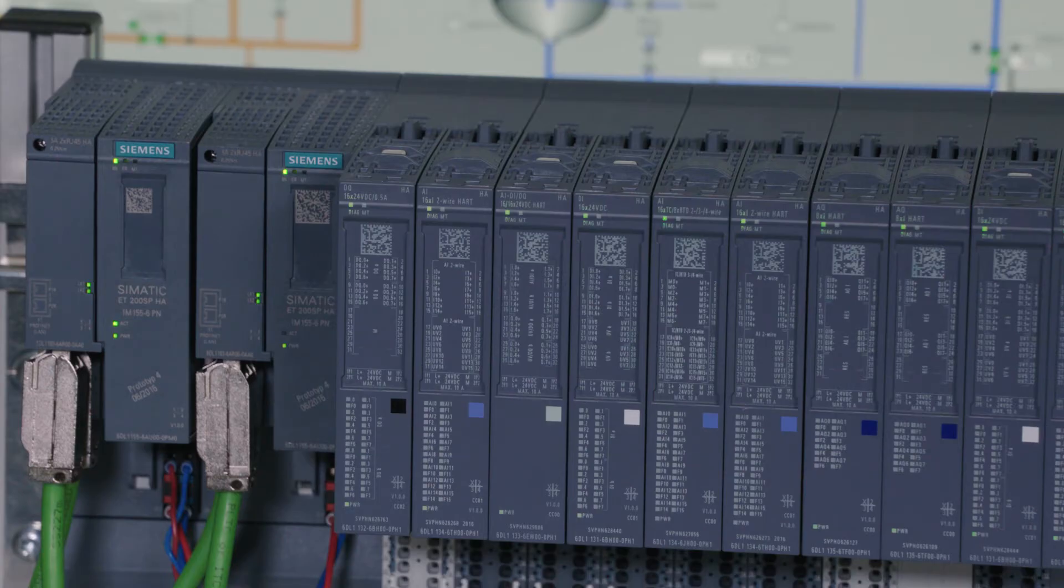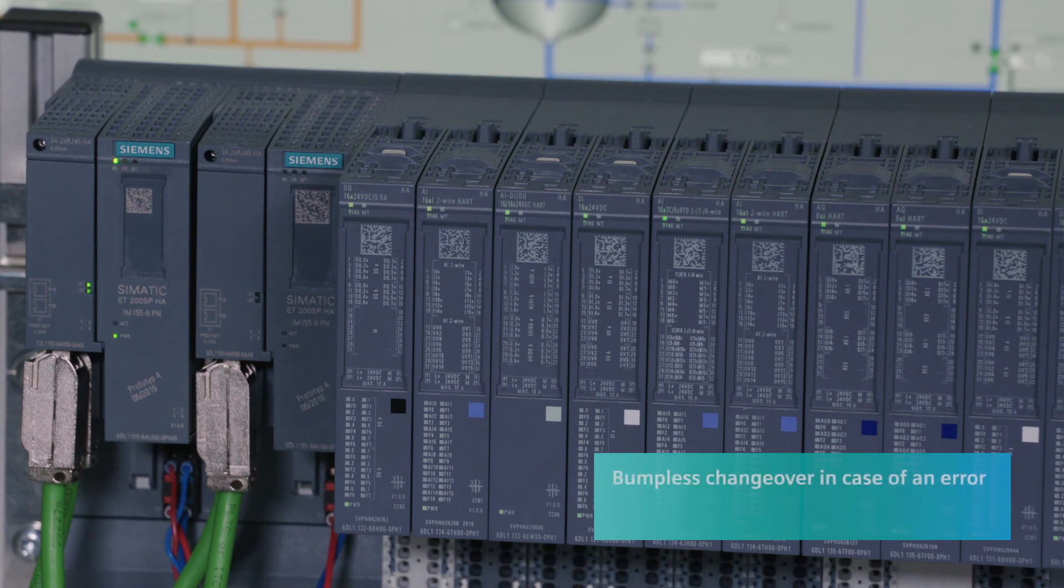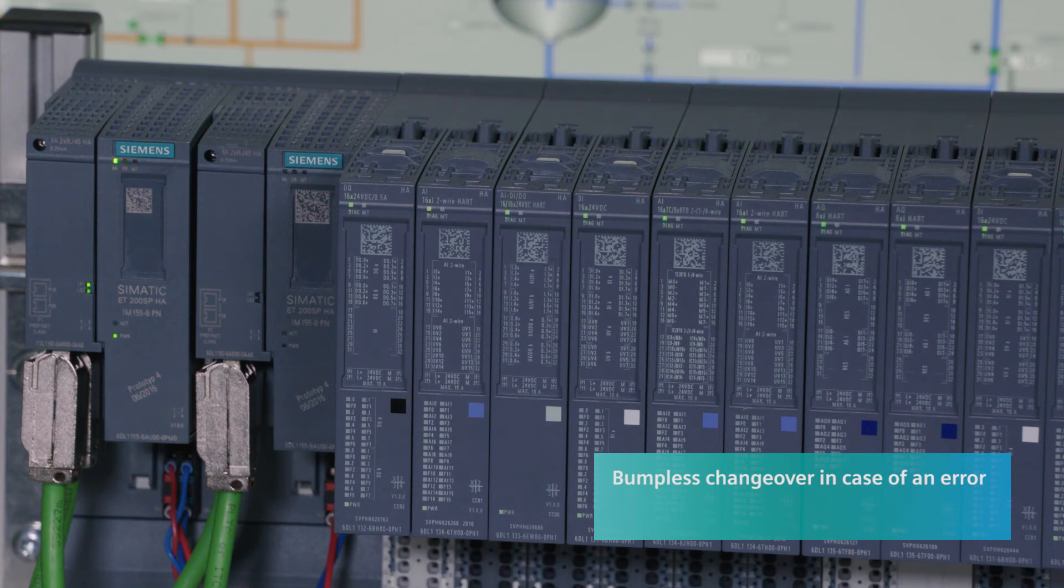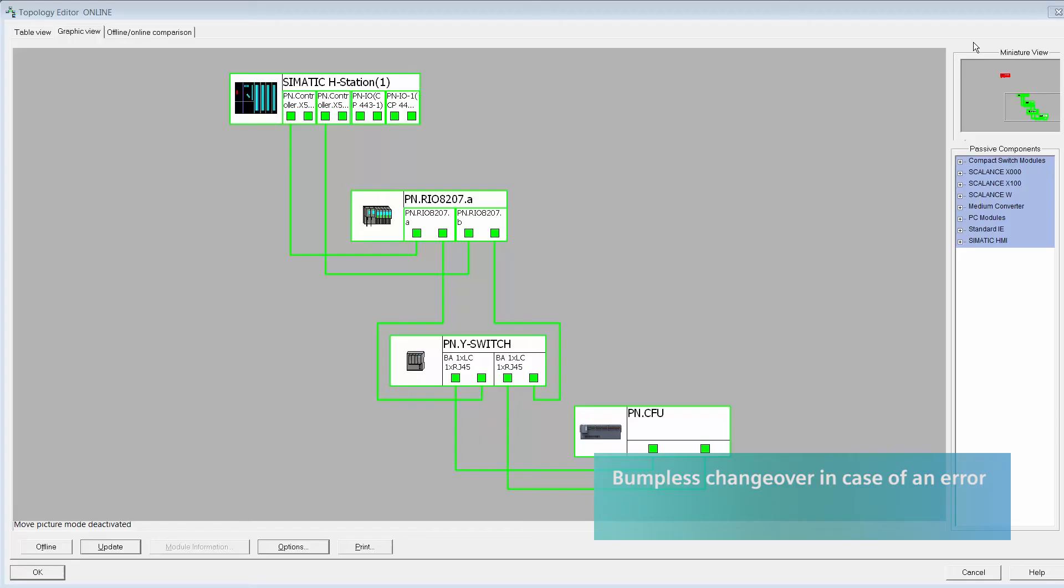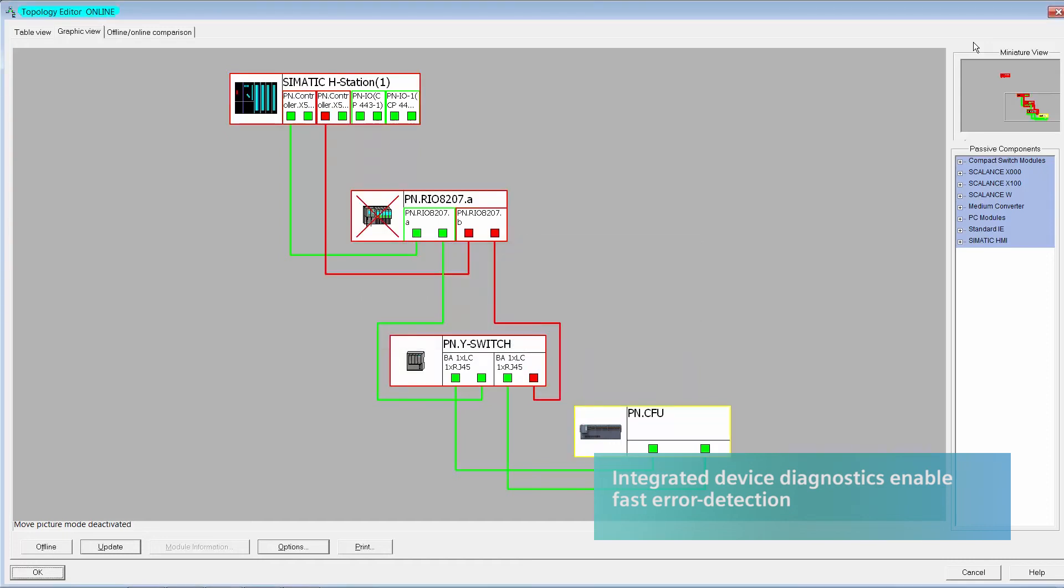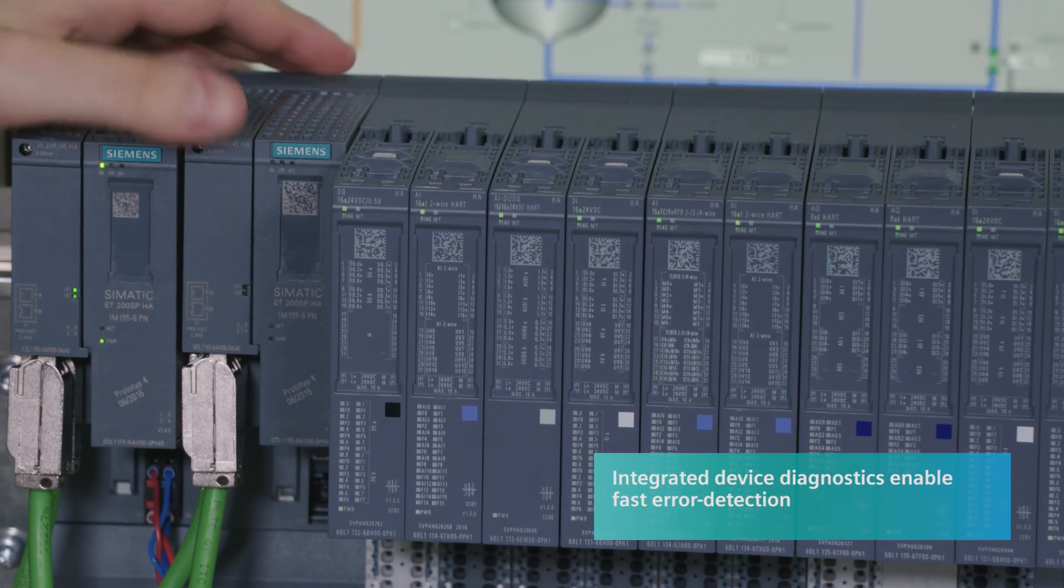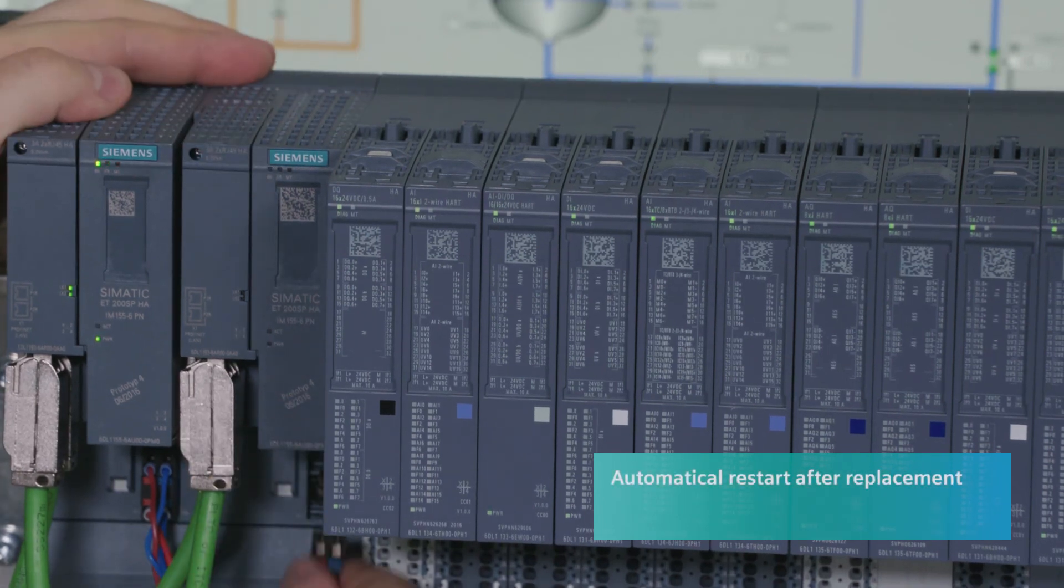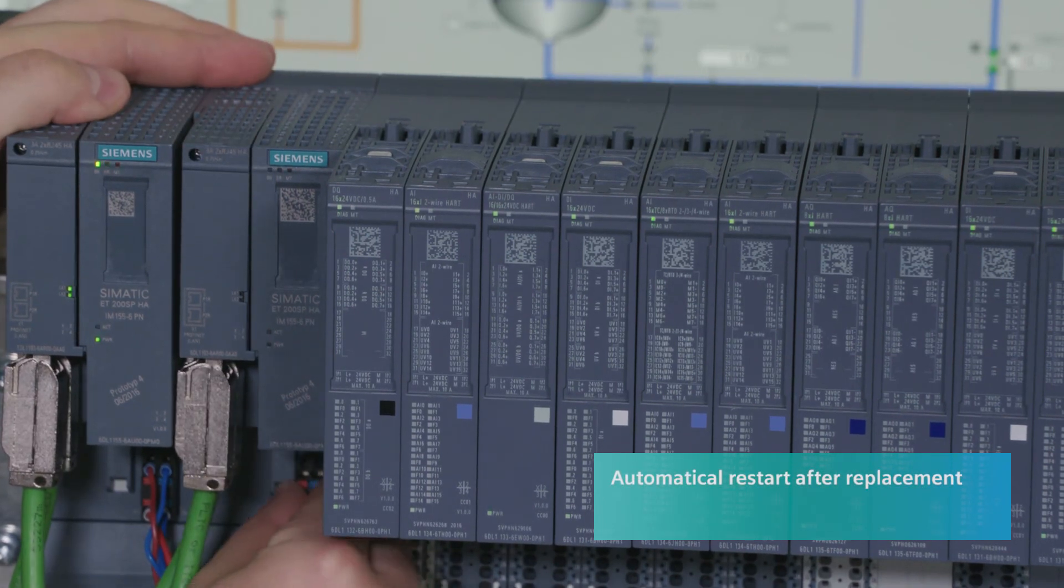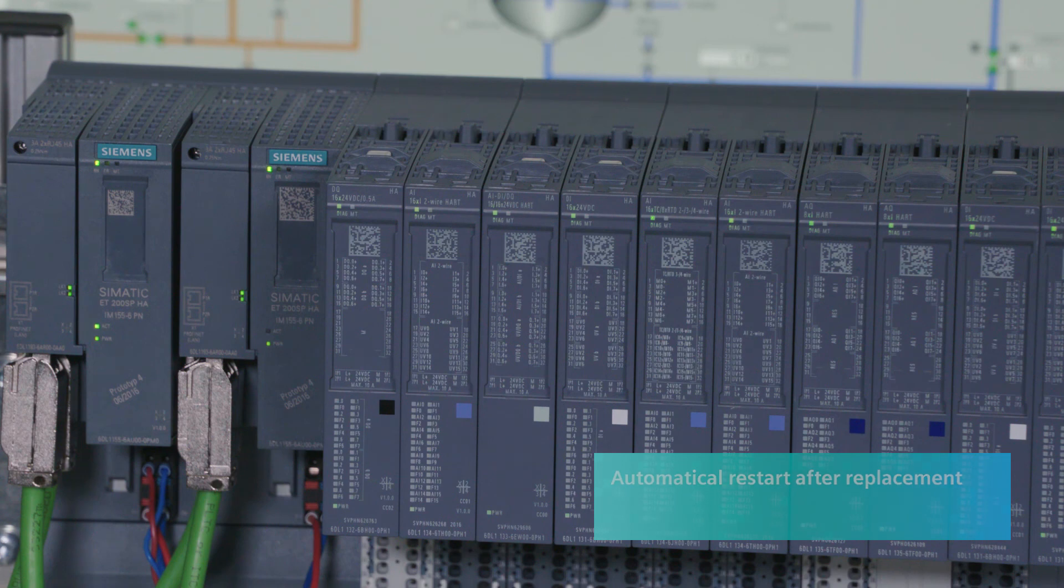I would like to use a brief use case to illustrate how easy it is to work with PROFINET. Imagine that a redundant interface module of the high-availability SIMATIC ET200 SPHA remote IO experiences a failure. Modular system redundancy R1 ensures a bumpless changeover to the redundant interface module. With the help of the integrated device diagnostics such as the topology editor of SIMATIC PCS7, errors can be identified quickly and easily. Thanks to automatic neighborhood detection, the system automatically assigns startup parameters such as the device name and the IP address to the replacement device. With this feature, the device replacement is completed quickly and easily.